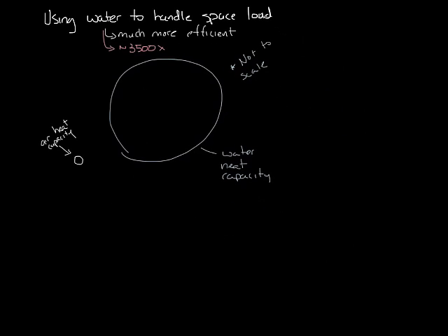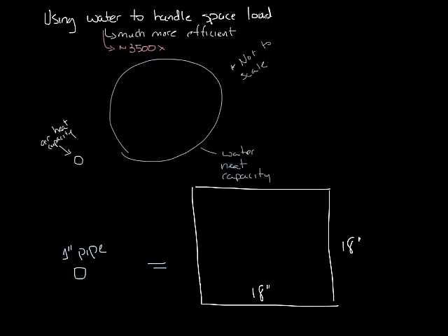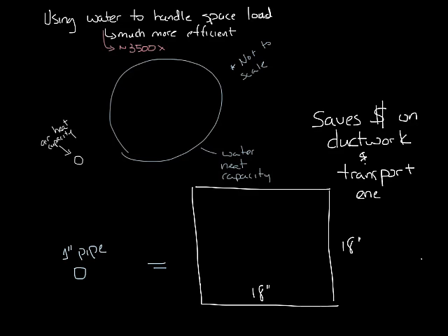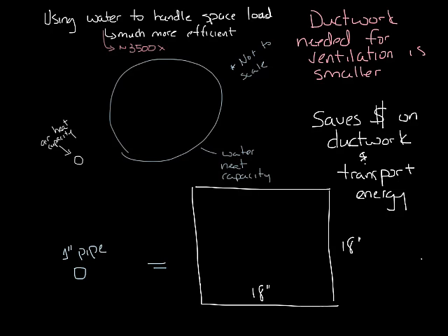Stated another way, a 1-inch water pipe transports the same heating and cooling capacities as an 18 by 18-inch ductwork. This huge difference means that you can cool the space using piping that's 1-inch versus running larger ductwork throughout the building. This saves on the material cost of the ductwork in the building. It should also cost you less to transport that energy through the 1-inch pipe than the 18 by 18-inch ductwork. In a chilled beam system, you still have to run ductwork for the ventilation air, though. But even though there is ductwork, it is much smaller because you only bring in enough air to handle the ventilation requirements, not handle the entire load of the space. The ductwork is more likely to be about 5 or 8 inches coming into the chilled beam supply air inlet.